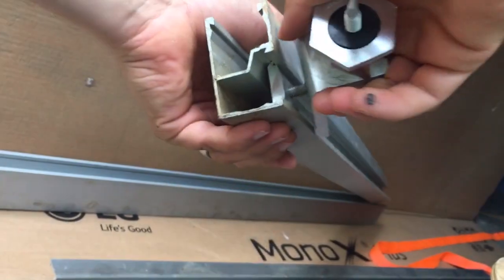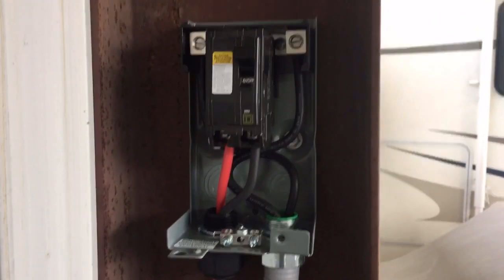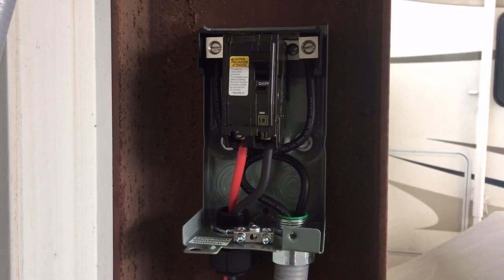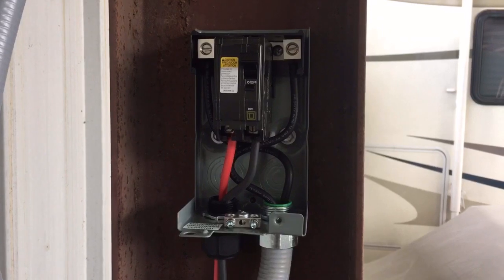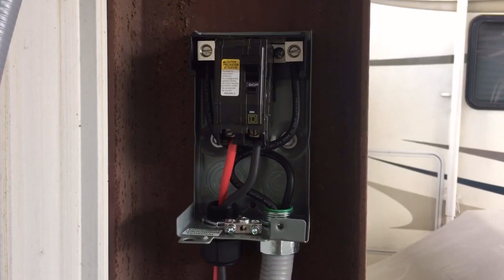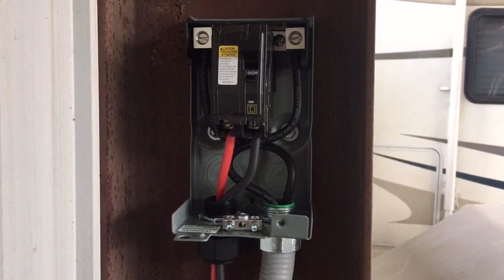There's my DC conduit run with liquid-tight metal flex, and this is just a Square D QO disconnect. It's only doing 30 volts and about 8 amps so not too worried about it. QO breakers can actually handle 48 volts — not a lot of people know that. I'll show you the charge controller in a second.